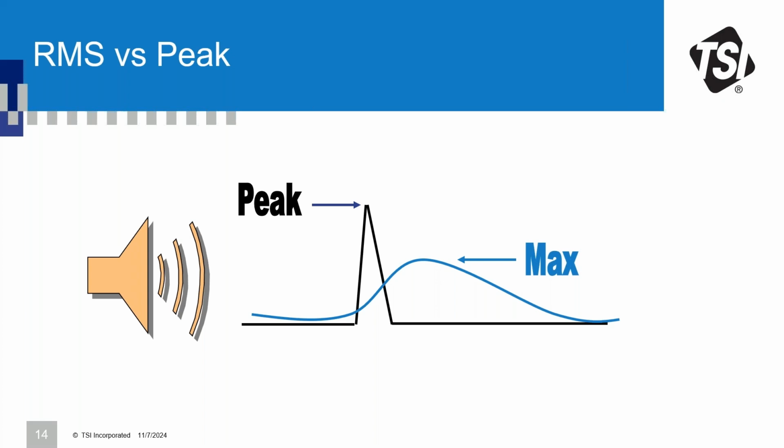Okay. Now more on the peak response. RMS versus peak, right? When there's very high amplitude or short duration peak sound, like a gunshot, the RMS detector cannot accurately track the level. So the diagram over here shows you the difference between the peak response, which is far higher than what the RMS max would display or show you on your SoundPro, right?